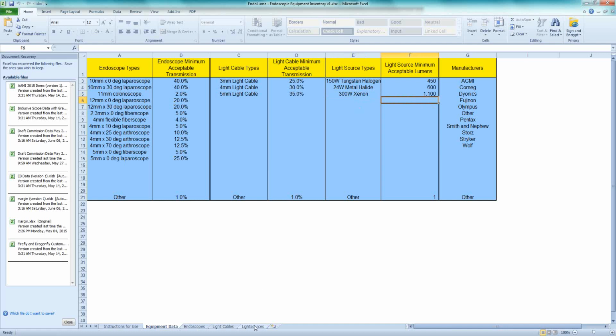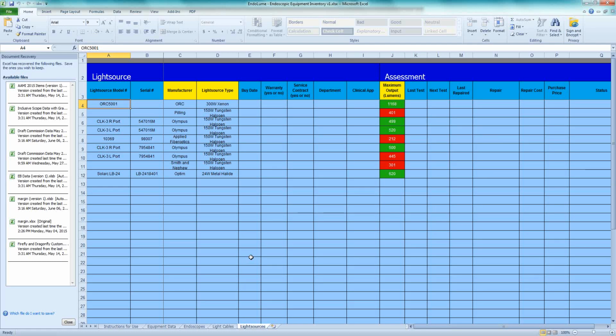So if we look here in the working tab for the light sources, we see you can type in your model number and serial number. The manufacturer and the light source are drop downs from those other tabs. We see this top one is listed as a 300 watt xenon. Its output is measured at 1168 lumens, and we said 1100 was the minimum, so it shows as green.